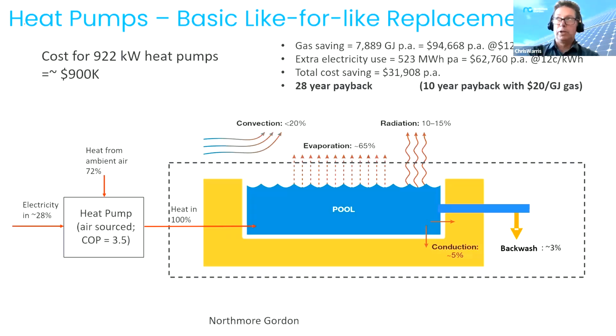So it would eliminate the gas use, but it would consume its own electricity to do the same heating. And if you look at the numbers, there is a cost saving there. If you're looking at $12 a gigajoule of gas and 12 cents a kilowatt hour of electricity, which are typical prices that we've seen up till about a year ago, there is a cost saving, but it's a 28-year payback. The payback does improve with the higher gas price, but you're still looking at a long payback for doing something like this.